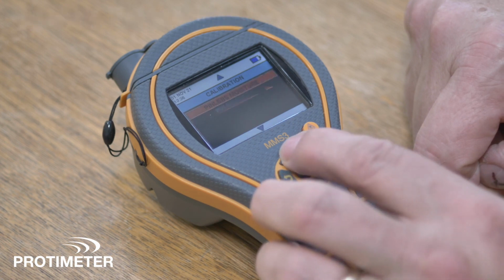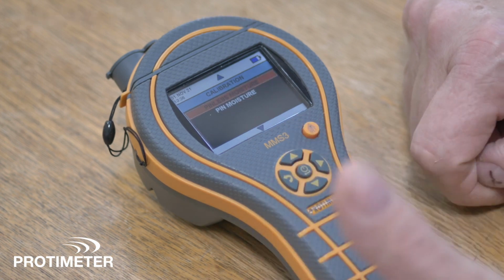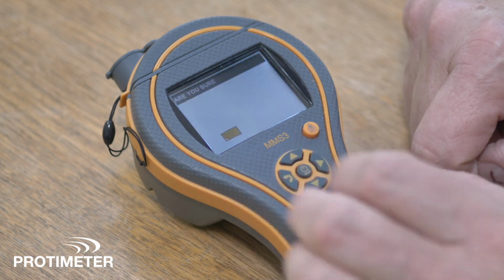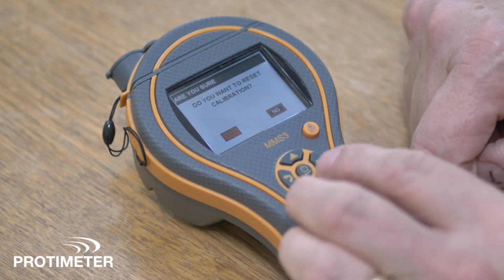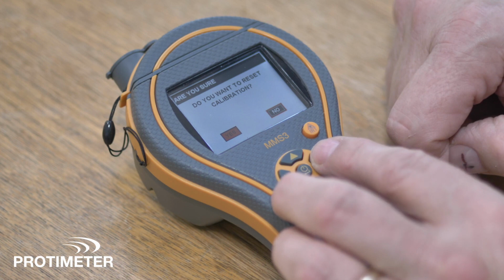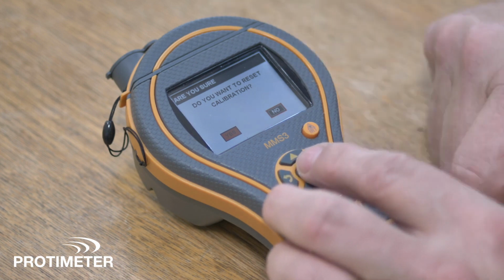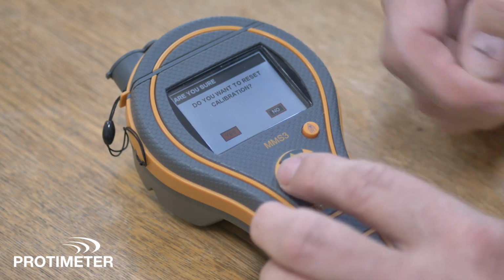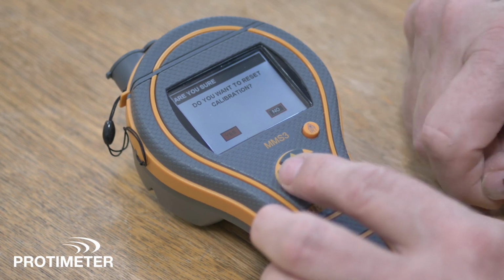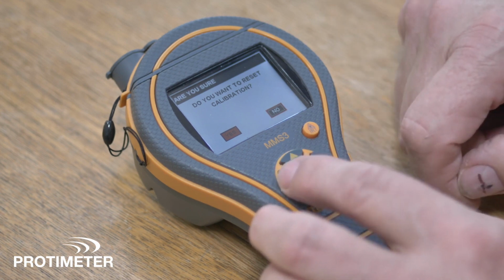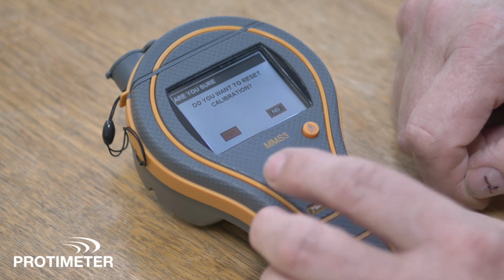We also have the ability to recalibrate the pinless mode. We select that, then hold it in the air, a meter away from any other object, and recalibrate it. This allows very quick and easy recalibration of the non-invasive mode. With the MMS2, you'd need to return it to the factory.